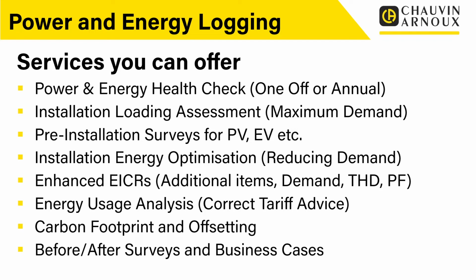Similar issues arise with EV charging. If you're adding electric vehicle charging, particularly a big fast charger, you need to know the electrical installation is capable of doing that. A loading assessment is a good way of checking this. You might find it wouldn't be capable of doing it in the evening, but there's a set point at night - say 5 hours - where it would actually be suitable. So then you might design the installation with a timer, relays, or contactors.